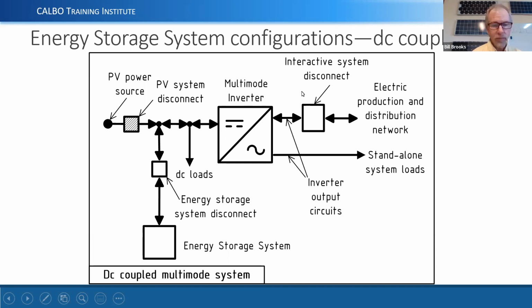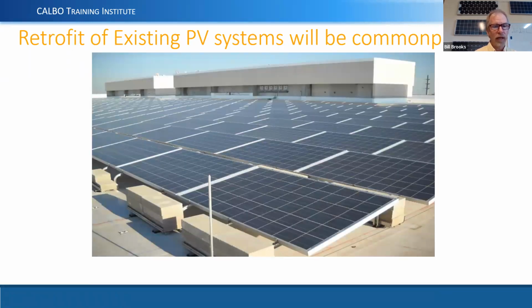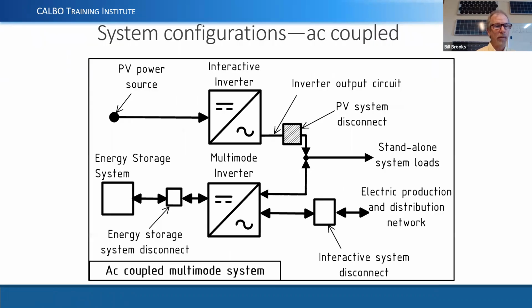So the disconnects that are over here, whether they're going to the interactive side of the inverter or to the standalone loads, those are not PV system disconnects. They are interactive disconnects, or they could be load disconnects. The actual source disconnects in this example are all on the DC side. Retrofitting existing PV systems will become commonplace. A lot of those systems are going to be configured in this manner.